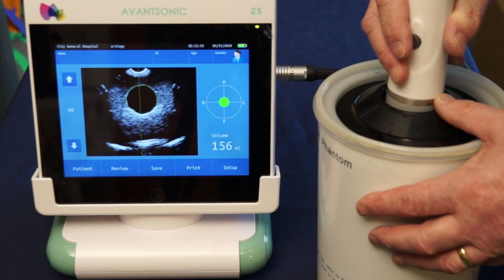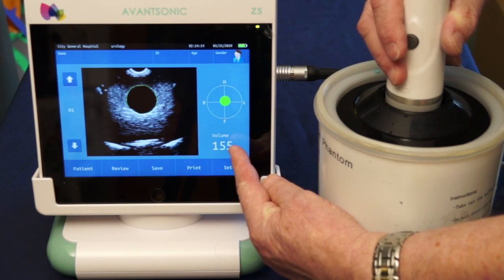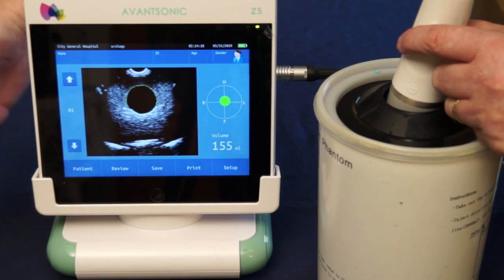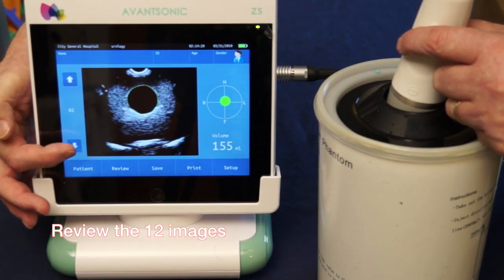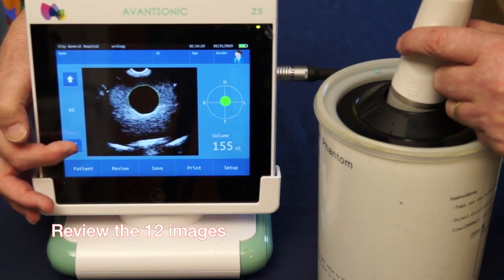Press the button again to actually enter scanning. It counts to 12 and gives the reading at the bottom right-hand side again. It is good practice to review the 12 images that you've taken, and by pressing the up and down arrows you can view each of these images in turn.